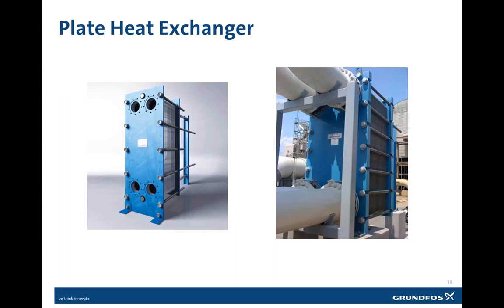So to talk a little bit about what a gasketed plate heat exchanger, or a plate and frame heat exchanger, is: a plate heat exchanger is just a device that transfers the BTUs from a source to a load without the fluids actually coming in contact with each other. The plate heat exchanger is a compact device which can be located either indoors or outdoors, and insulated or not, depending on the application.